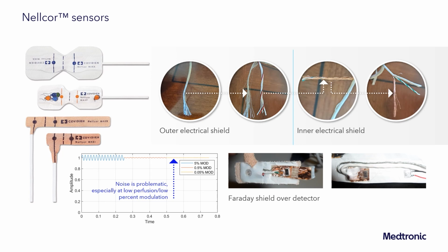attached to the LEDs. And if we look there, we find another inner jacket. And if we cut that inner jacket open, what we see is that there's a second, or an inner, electrical shield. And that inner electrical shield covers the photodiode conductors. Now, the photodiode, or the detector, is also covered with something that's been specially designed to block electrical noise but allow light to pass through it, and that's called a Faraday shield.